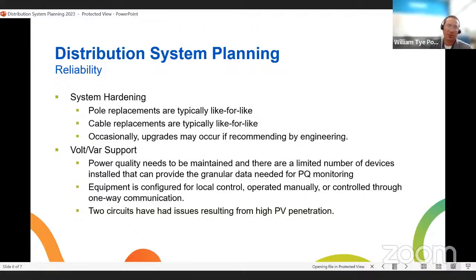And then our volt VAR support: we have power quality needs to be maintained within the required power quality limits, voltage limits plus or minus 5%. There are harmonics and things like that which need some attention on occasion. We do have a limited number of devices installed that could provide power quality monitoring - we're talking on the order of minutes. If we need to get data that is every second, sub-second, or sub-cycle, then we would again have to do a PNM dispatch and install power quality equipment, and manually retrieve the data as well.